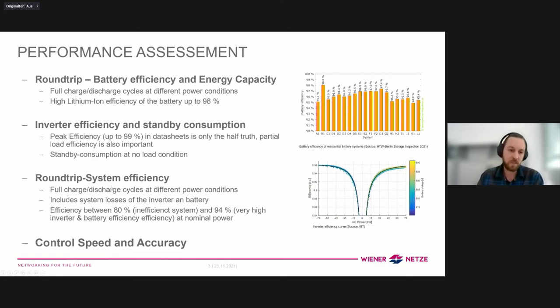At the end, we can also do a round trip system efficiency test, which combines both loss mechanisms: inverter losses and battery losses. You really have to be aware that the total round trip efficiency for one charge-discharge cycle is usually not higher than around 94% for the inverter and battery system together, because sometimes you see quite high values in the data sheet.